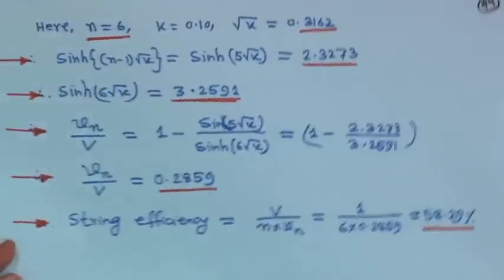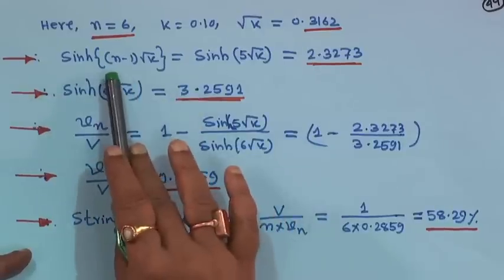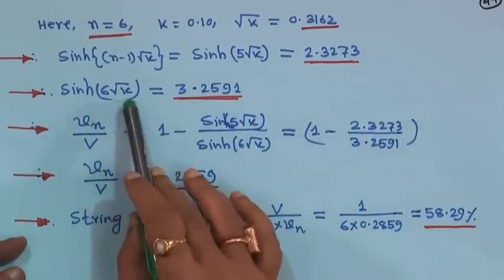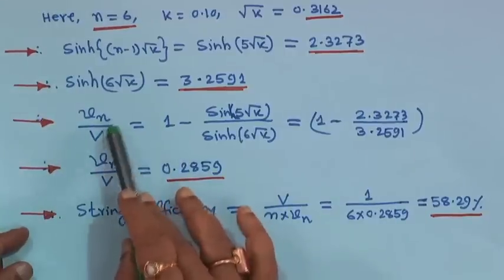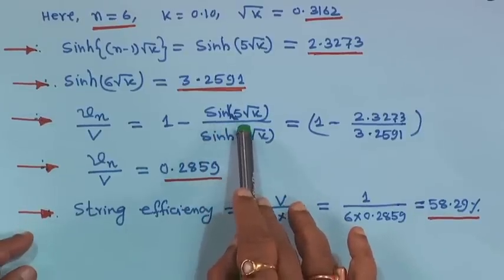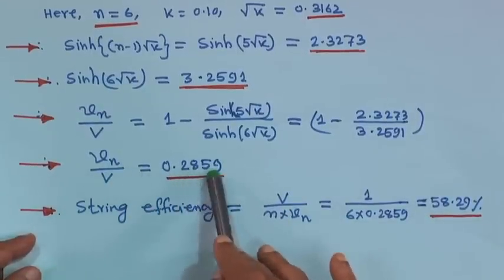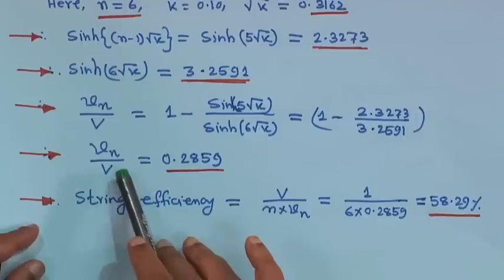It is given that n equals 6 and k equals 0.1, so √k is 0.3162. Therefore, sinh((n−1)√k) equals sinh(5√k). With √k equal to 0.3162, multiply 5 by this and take sinh — it becomes 2.3273. And sinh(6√k) when n equals 6 becomes 3.2591. Therefore, V_n/V equals 1 minus sinh(5√k) divided by sinh(6√k). Substituting all values gives V_n/V equal to 0.2859, where V_n is the voltage across the last insulator nearest to the conductor.